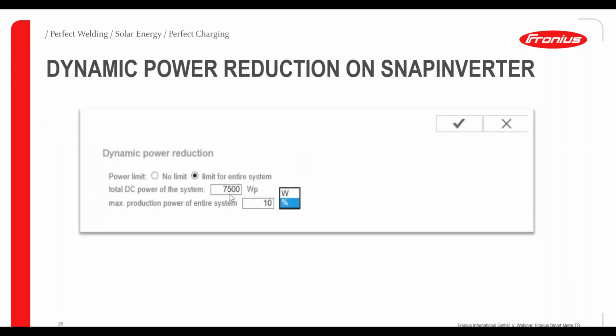So if we have a closer look at that, here you enter the total power of your PV system, in this case 7.5 kilowatt. And then you can enter the production power of the entire system, either as a power range or in percentage. So you can decide how you want to limit. I know there are some regulations in different countries. I know in Germany, for example, you are not allowed to feed in more than 70% of the total power of your PV system. And that way you can limit. Or even here in Sweden, you may want to limit how much you feed into the grid. That's the way you do it. Of course, after every change in the web interface, you need to save the changes before you proceed. Important.